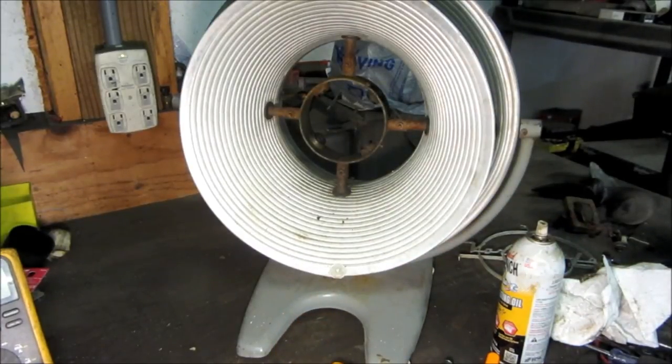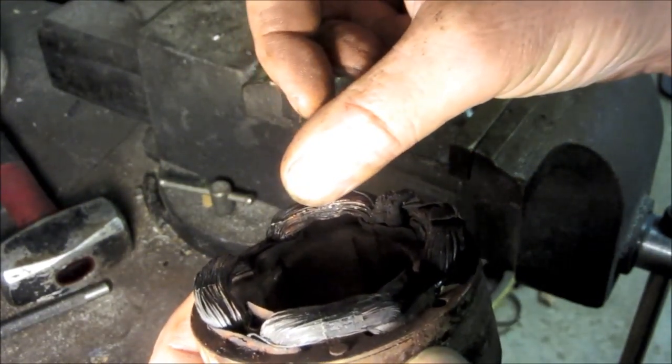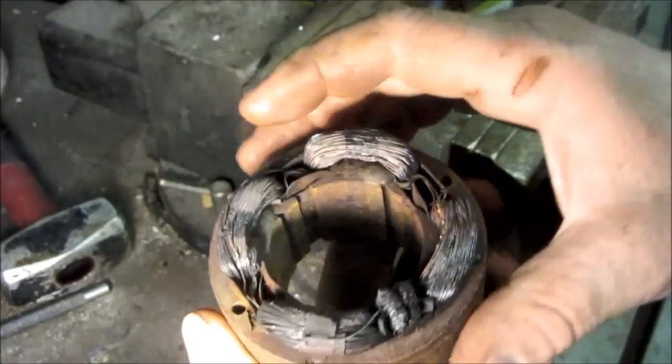Customized motor there. Well, much I hate to say it, this one is toast. You see where it's arced right there? That's a break in the winding and all this is charred and separated, so this one's burned out.